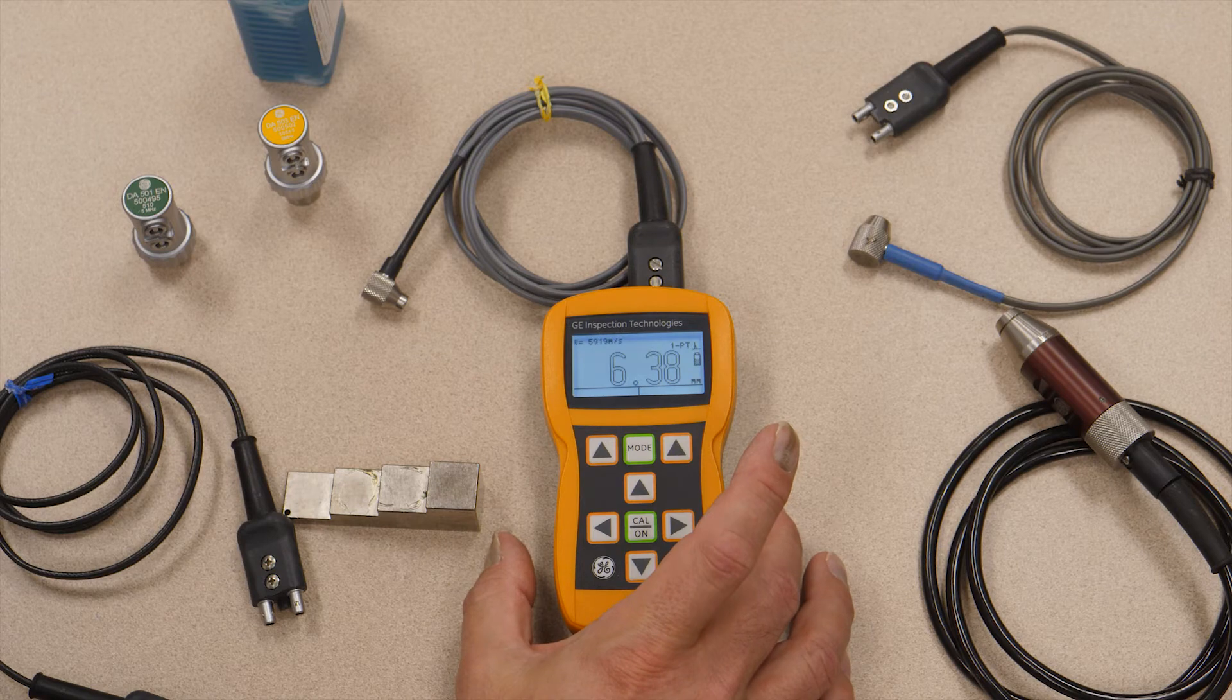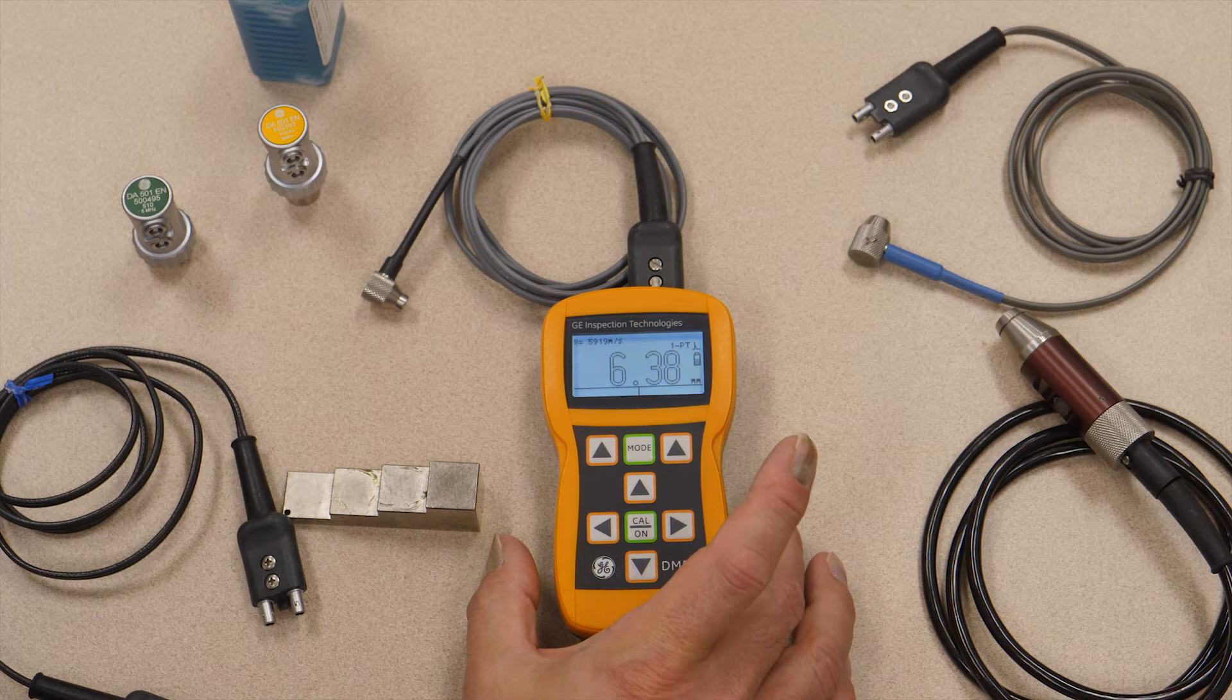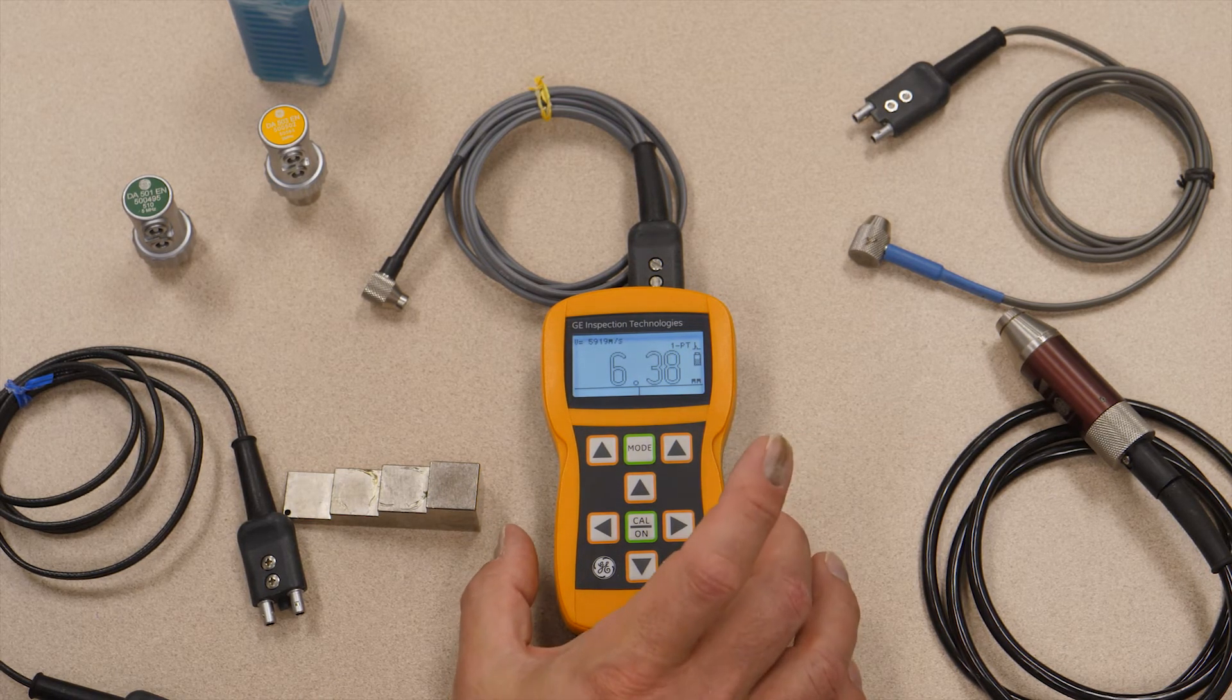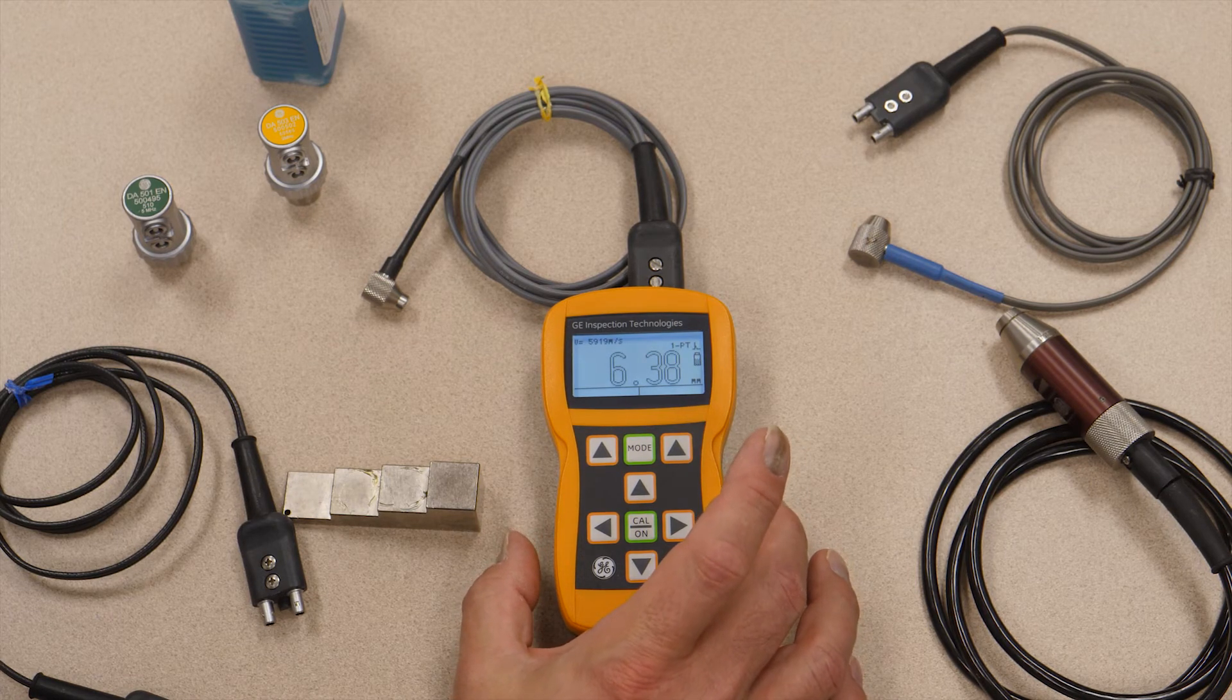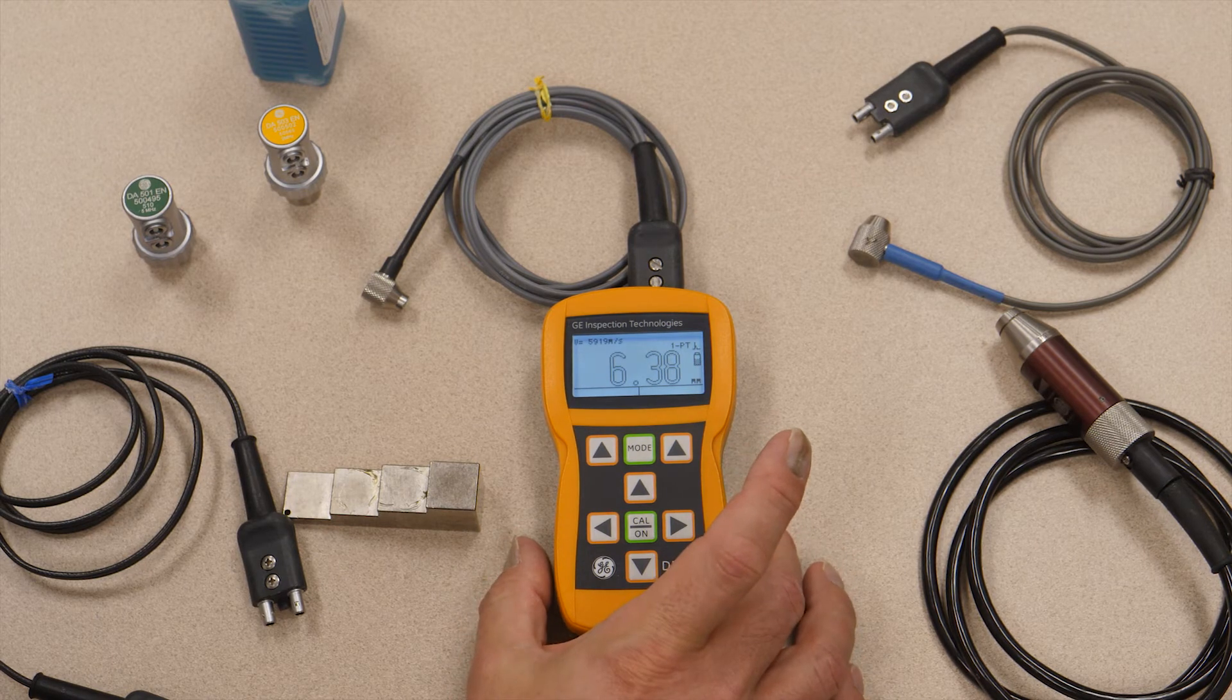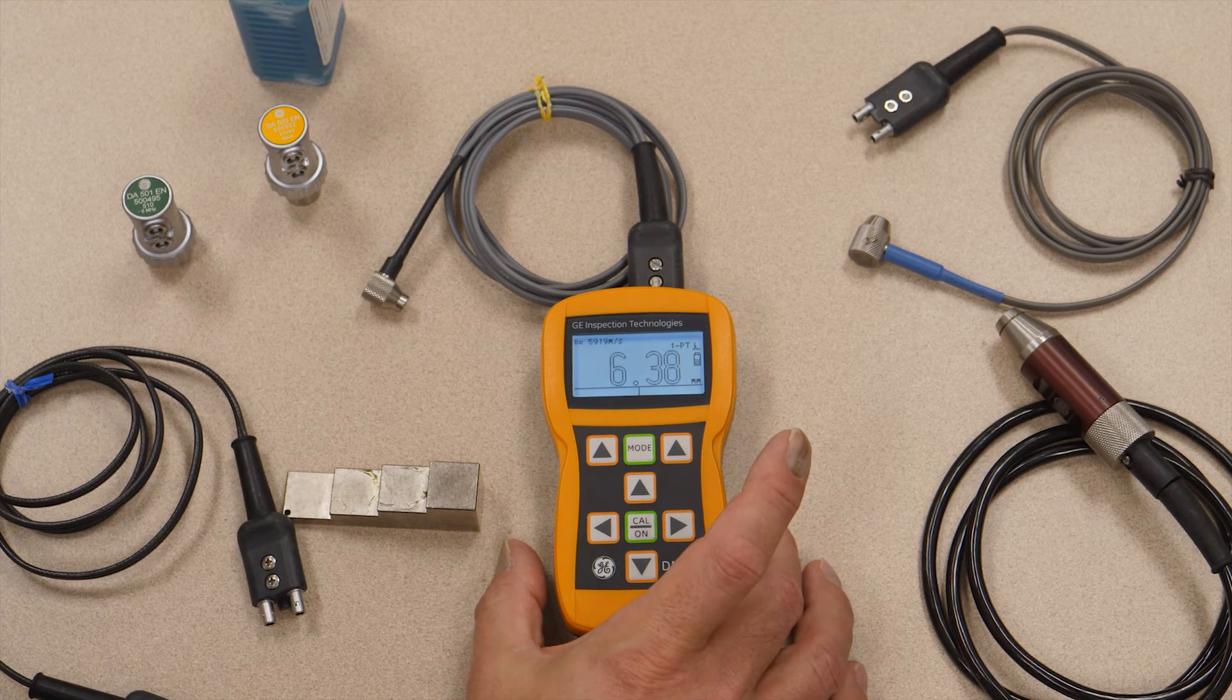And because the paint is typically about one third of the sound velocity of steel, 10 thousandths of paint will increase your thickness measurement by about 30 thousandths of an inch. So we offer the dual multi-mode to compensate for that. It takes multiple back wall measurements through the steel only, ignores the coating thickness, and you get the raw base material thickness.